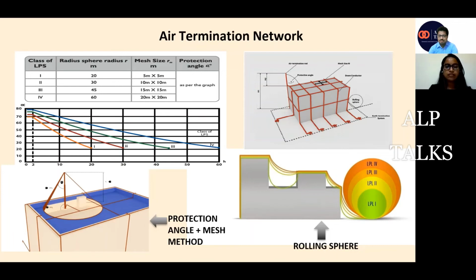As I have told you earlier, there are 3 methods of designing: the rolling sphere method, the mesh method, and the protection angle method. The protection angle method is used for buildings less than 60 meters in height at level 4. For level 3, the maximum we can go with the protection angle is a 45 meter building. For level 2 it is 30 meters, and for level 1 it is 20 meters. If I am designing a building at level 1 and its height is 25 meters, then I cannot design it with the protection angle method. I have to go with the rolling sphere method.